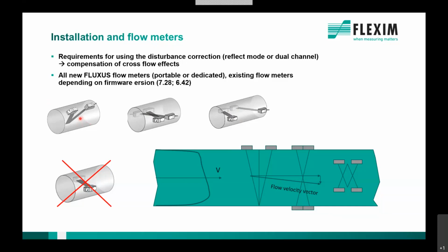Most installations are done like that because it's the easiest way of installing a transducer. Or if it's not possible to have a reflect mode installation due to application influences, then a dual channel meter is to be used. In that case, you can use the disturbance correction as an option and compensate for it. If you have a single channel meter and have to install it in direct mode, you can't use the disturbance correction, because that meter is affected by the cross-flow effects. Cross-flow effects can be a higher influence than what we actually correct by the disturbance correction, so it doesn't make sense. It may even go in the wrong direction when compensating it. That's why it cannot be used for single channel meters in direct mode or other uneven numbers of sound paths, like 3 or 5 sound paths.